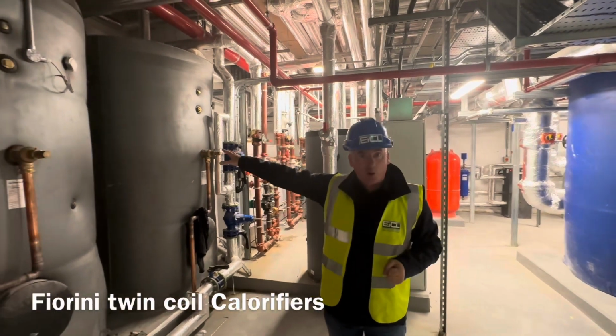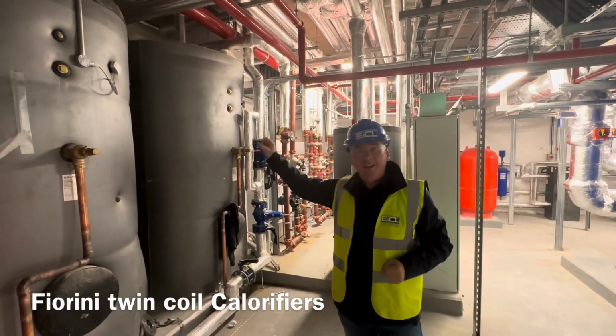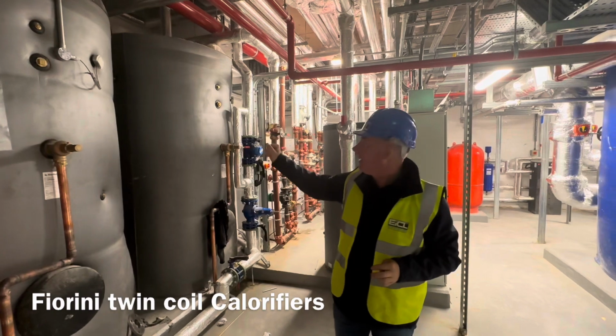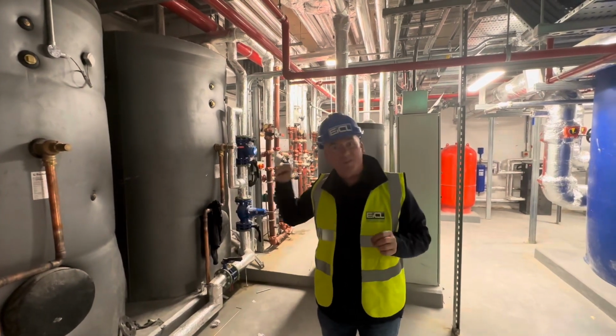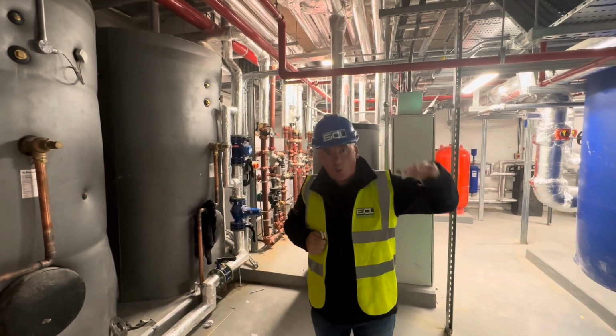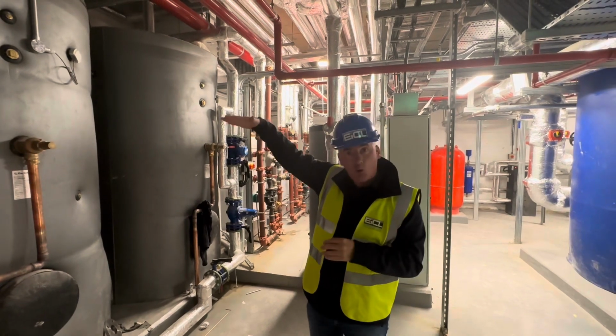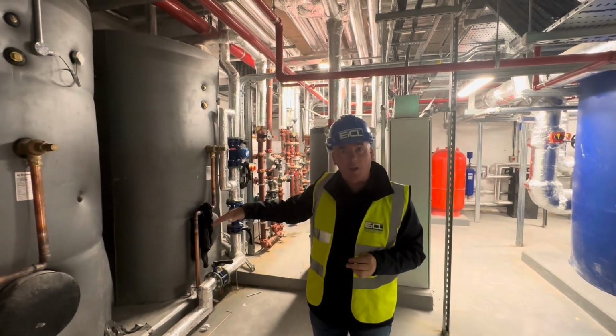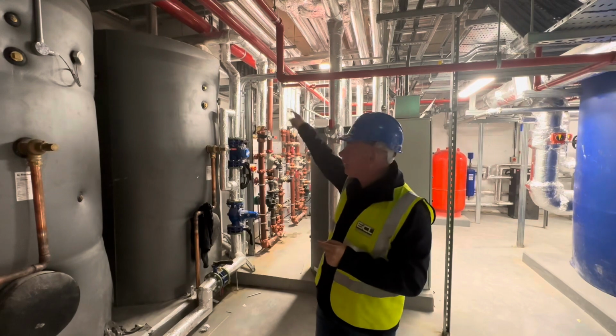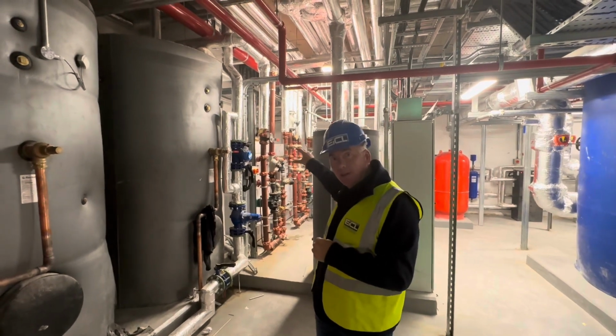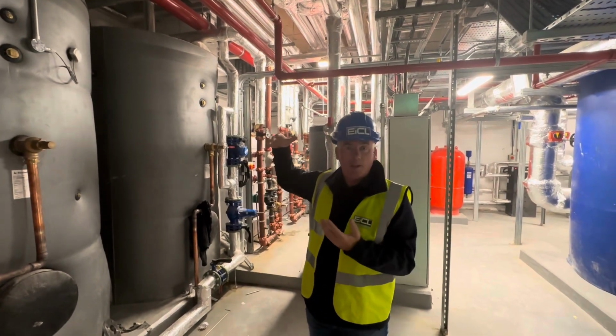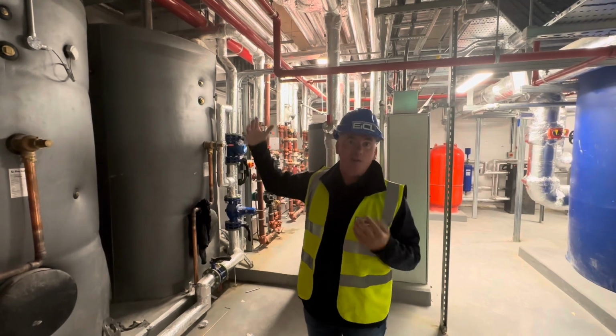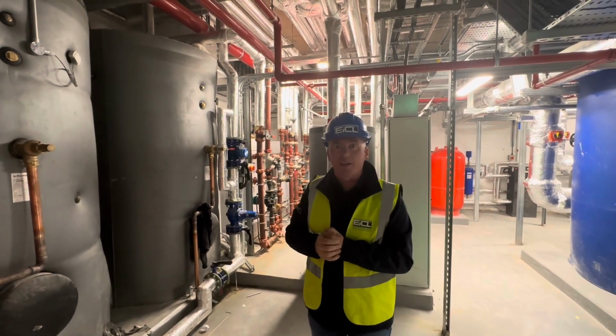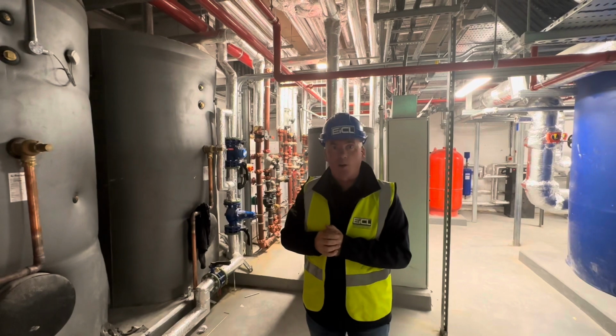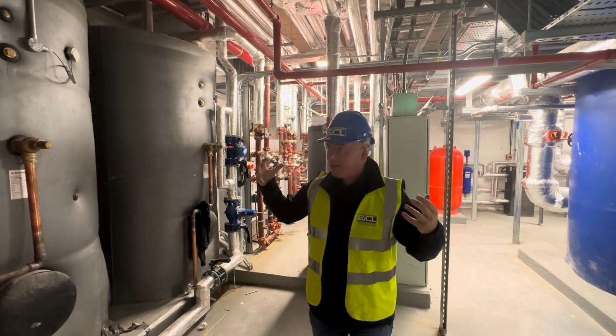And of course we have the calorifiers also from Fiorini. These are a twin coil calorifier, where we have the first coil, which is fed from the LTHW, the lower temperature, which will get us to about 2/3 temperature, so typically from about 10 degrees supply to about 40 degrees. And then we have our secondary coil coming from the WWB, which will boost the temperature from typically about 40 to 60 odd. Obviously we need to go above 55, 60 for Legionnaires, and to satisfy the high temperature that's important. So that's everything that we have here.